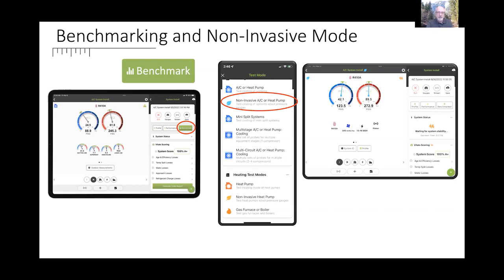Once I've benchmarked it, I can come back to this system for years and years to confirm it's still within the benchmark, and if it's not, then maybe I have to tap the system now to figure that out. The amount of times we're tapping systems is just crazy when we don't really need to. But to do a non-invasive mode -- since we can use temperatures and pressures together, or calculate one from the other -- we need to know the system was operating correctly originally.